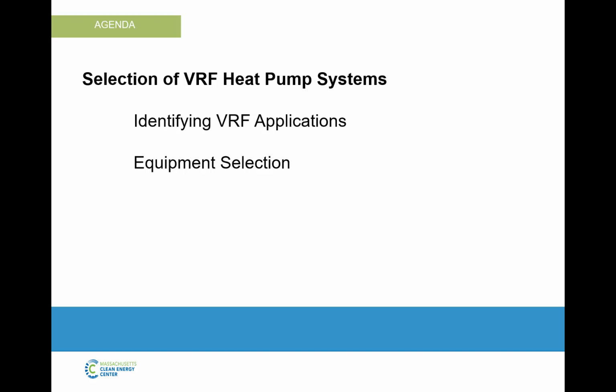The knock on VRF equipment is, okay, now maybe instead of one large central unit on the roof, I have 20 VRF systems on the roof. That's 20 compressors, 20 fans, 20 separate modules. So yes, that is some more attention that needs to be paid because you do have more modules. For your specific building and how you operate, you have to consider the other side of that. One, the good thing is that without a central system, if one of those units has a problem, you don't lose heating and cooling in your entire building, only that section. And then it's more simplified maintenance.